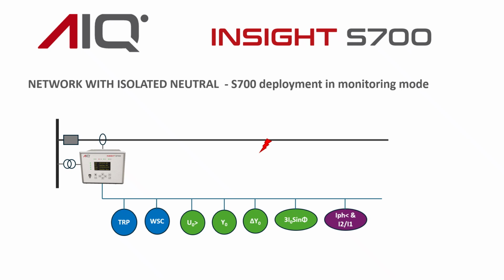For networks with an isolated neutral, TRP, WSC, zero sequence over voltage, zero sequence admittance, Y0 and delta Y0 can be applied. The earth fault current for systems with isolated neutral is characterized by its strong reactive component. Therefore, I0 sin phi is a traditional technique and is available. Lastly, the open conductor based on the ratio of I2 over I1 is universally applicable for all networks.